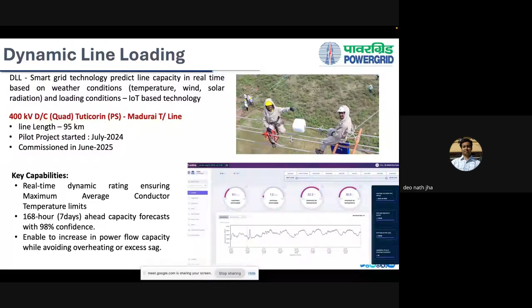So the capabilities are that it has real-time dynamic rating ensuring maximum average conductor temperature limits. Then there is also a 7-day capacity forecast with 98% confidence. So sitting today on 12th January, I can know how much power flow I can send across that transmission line till 19th January, because I know the weather conditions forecasted 7 days ahead. And it enables an increase in power flow capacity while avoiding overheating of the conductors or excess sag.